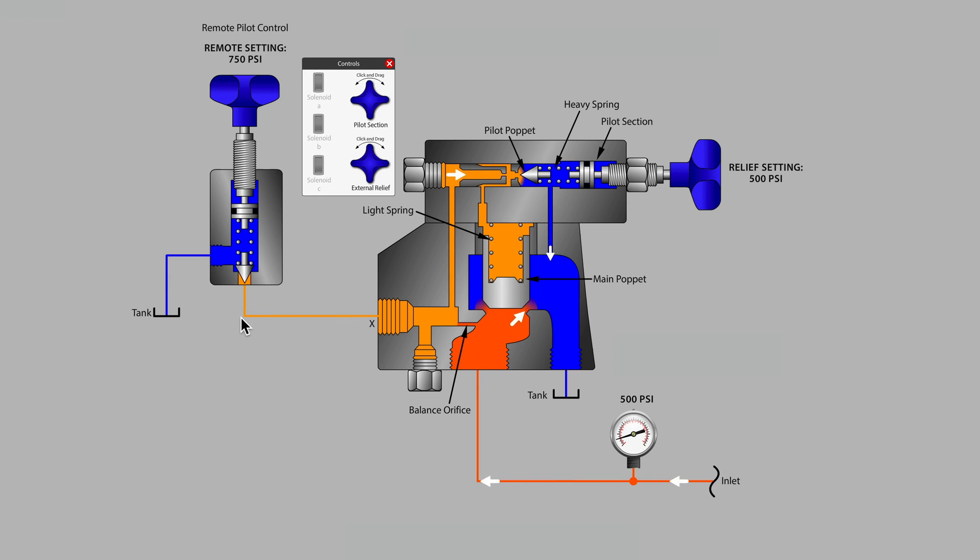This is essentially a direct acting relief valve, usually with a fairly fine thread, and it allows the operator to make adjustments to the maximum system pressure, which remember is being controlled over on the main poppet, but it allows the operator at a distance to set that main pressure.